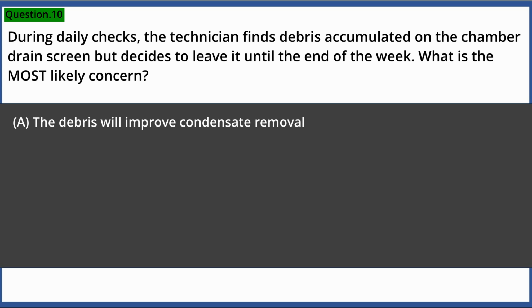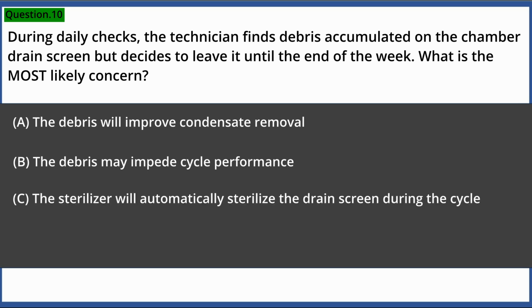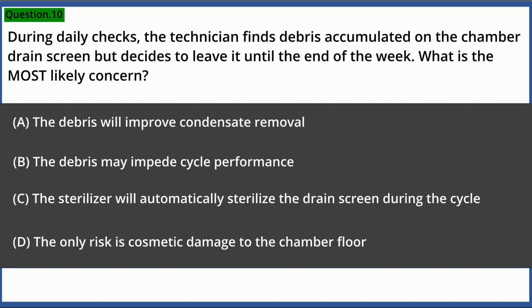A. The debris will improve condensate removal. B. The debris may impede cycle performance. C. The sterilizer will automatically sterilize the drain screen during the cycle. D. The only risk is cosmetic damage to the chamber floor. Answer: B. The debris may impede cycle performance.